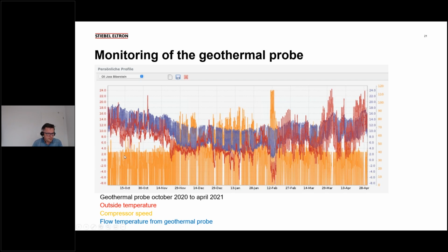You also see the modulating of the heat pump. So we start here in end of September, beginning of October. It's just running on the lowest RPMs, the inverter, and then it starts to ramp up and down until end of February, and then it's just again the lowest capacity setting. These couple of days here in February, like 5 days in February, were the design conditions. So we designed systems for this one, and it was like -8 degrees. The rest is just part loads.